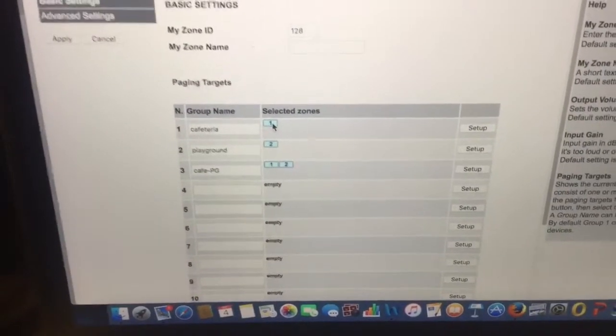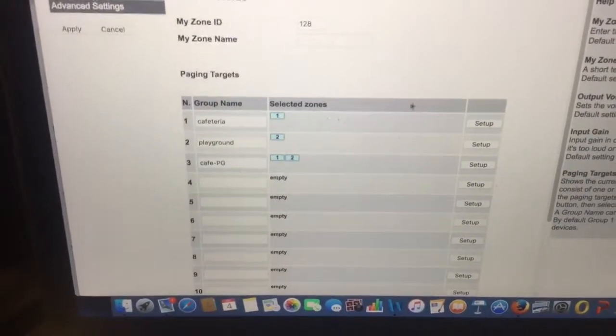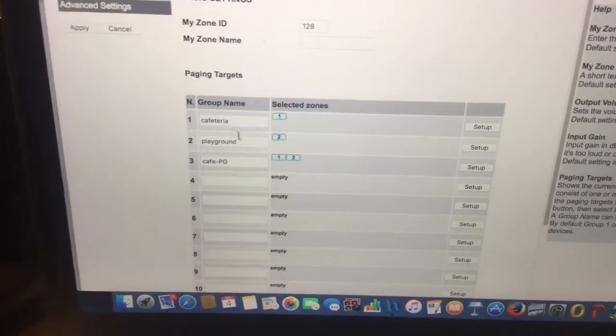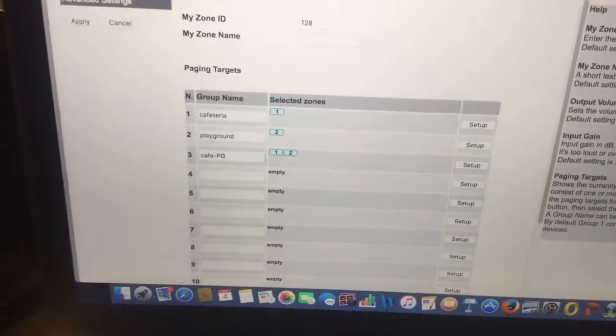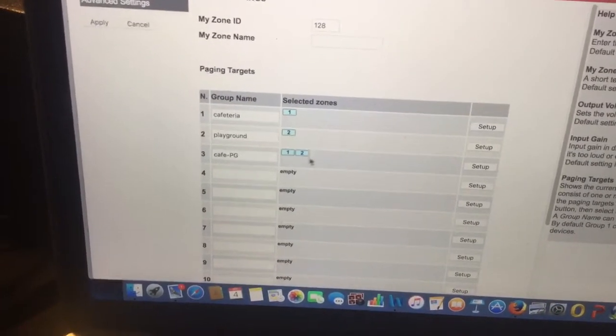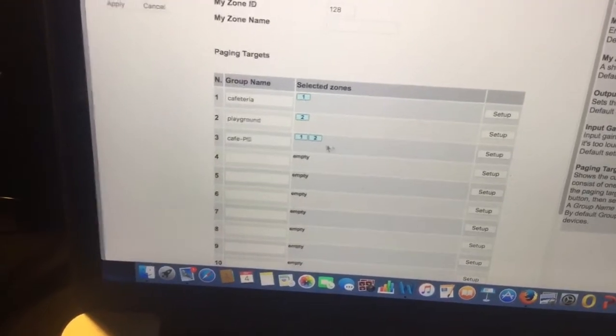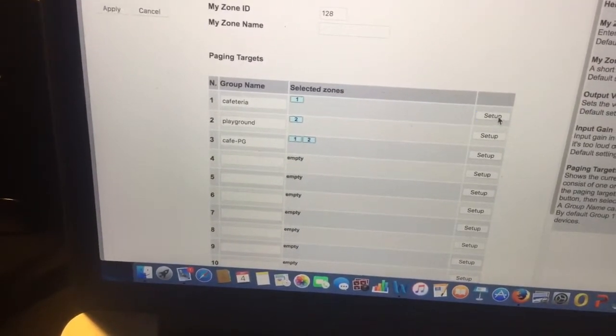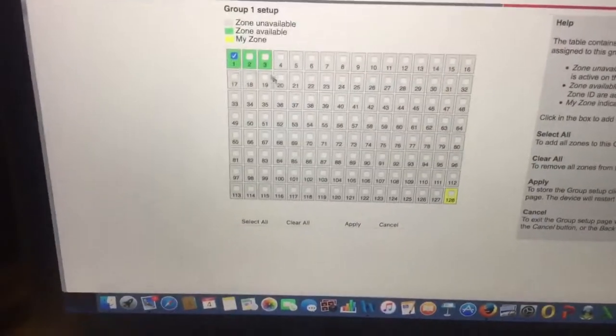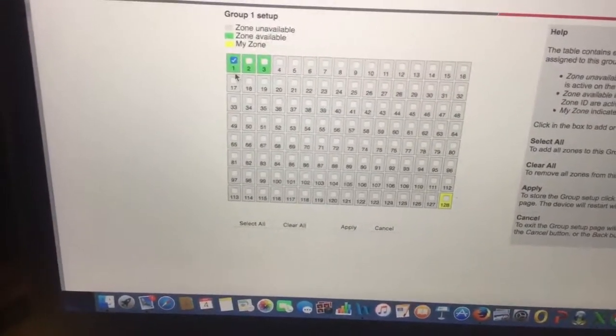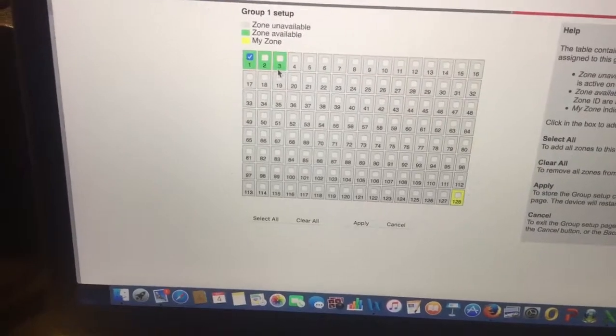You'll see each device, each endpoint is a zone. And what I've done then is they have you set up groups. So you can page to one zone, or you can put a couple of zones in a group and then page to two zones at one time, or obviously an all call. And you'll see when you configure up a group there, all of your endpoints that are active will show up, and then you select which ones you want to be in that group. So here's group one set up.